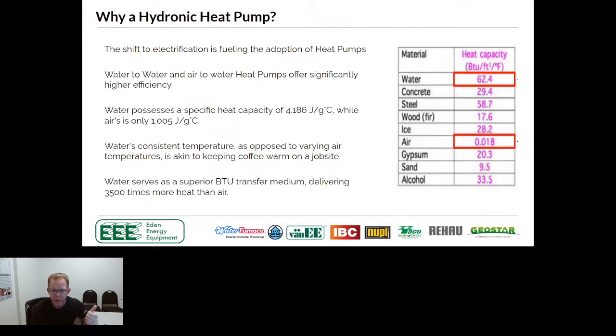as I'm illustrating right here, if you look at the heat capacity of water to air, it is 3,500 times more energy. So where I'm going with that is it was easy for me to run a 1/2-inch PEX line from my basement upstairs to my second floor, and then from there, from a manifold, feed into the different bedrooms with little tiny emitters to provide heating and cooling into those spaces, making them comfortable.